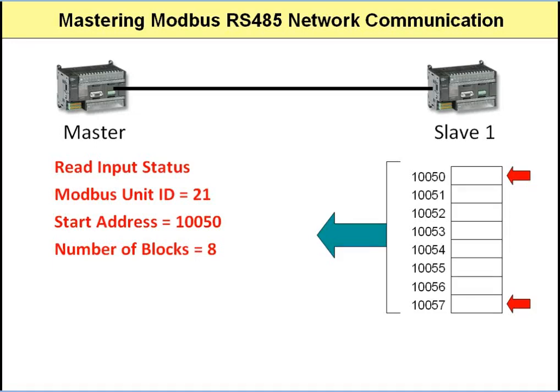This method of data transfer is very wasteful because the master gets data that it's really not interested in. But you have to remember that the Modbus protocol is an old protocol, and at the time, reading data in consecutive blocks was just fine. What's important to remember is that all of the read commands — read coil status, input status, input registers, and holding registers — work in the same way. The master always requests data in consecutive memory blocks, by specifying a start memory address and the number of blocks from the start.